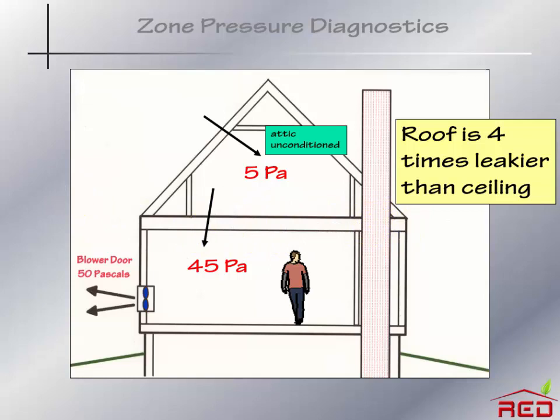Well, let's assume that I am a knowledgeable person. I come to this site, but I also don't have great integrity. What is going to happen to this value right here if I add attic venting? If I add attic venting to this house, essentially what I'm doing is making this pressure boundary leakier or less resistant to airflow. That means that the 5 pascals will go down.